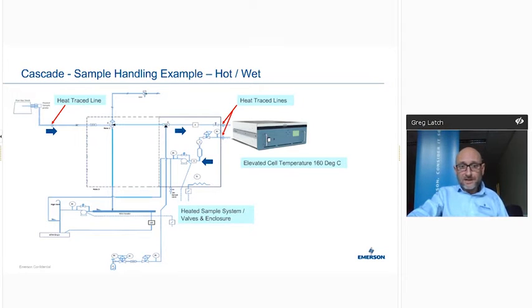You can also see briefly that there is a system there for a fast loop. So there's a pump downstream of what we call a header system there. Just showing you one loop. This particular application does have several loops, or points of measurement, stack points. And the main design for this, I'm showing you the one point, is the fast speed response, which we'll talk about in a second. So just to give you some examples, running at 160 degrees C, the vacuum regulator has a vacuum. We're running a slight vacuum at the technology point, which is the cell, leaving it at half an atmosphere. We spoke about the RC network, and based on the flow rates we can actually get through this system.